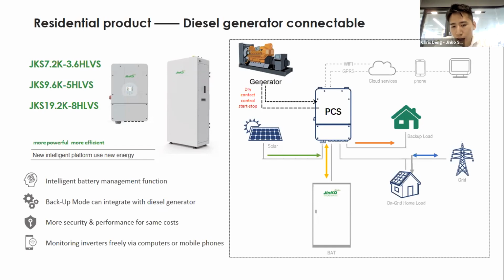From the chart on the right you can easily see how the system works. When the PV or diesel generator generates electricity, it comes through the PCS from the source side. PCS is similar to an inverter, but more professionally called power conversion system, transferring from AC to DC and DC to AC. When electricity generated from the PV or generator goes to the PCS, it will charge the battery, giving you a full charge and making sure it's stored safely. Also from the AC side, through the PCS, you can go directly to the backup load, and also to your home load or the national grid. That's how the system works.